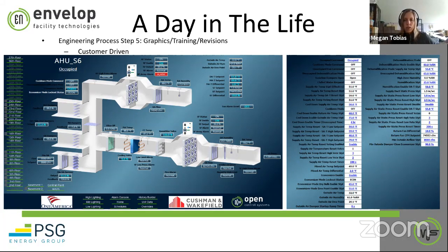For example, we'll have an optimum start sequence. When the building's occupied, everything's running, and when everyone leaves for the day, it generally goes into unoccupied mode. But for optimum start, it'll look at all of the different zone temperatures in a building, and based on outside air temperature and what the general normal time of day schedule is for the building, it can calculate the time it needs to start in order to be at a comfortable temperature in the spaces by the time people start coming in.